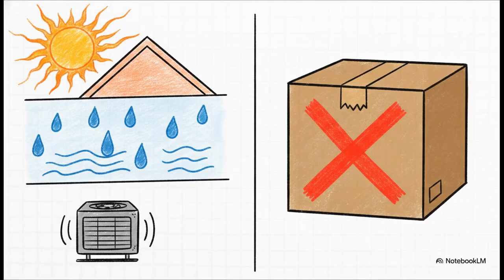Look, installing ductwork down here in Tampa requires way more than just a basic out-of-the-box setup because of some pretty severe environmental demands. First off, we're dealing with high humidity levels pretty much all year round. Second, extreme attic heat. I mean, during a Tampa summer, your attic isn't just warm, it is literally a scorching oven. And finally, because of all that, we have constant year-round AC operation. Your system rarely gets a break. These specific climate factors mean that a standard installation is practically guaranteed to fail you. It just won't cut it. You absolutely need a highly specialized approach to withstand this kind of environment.